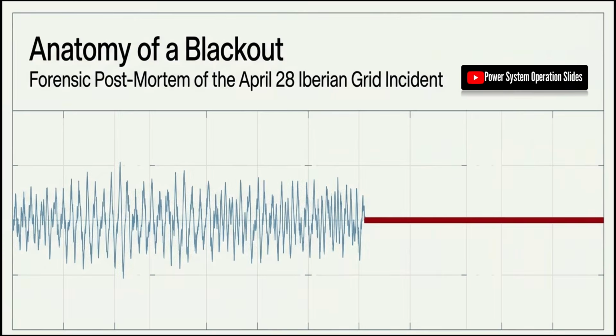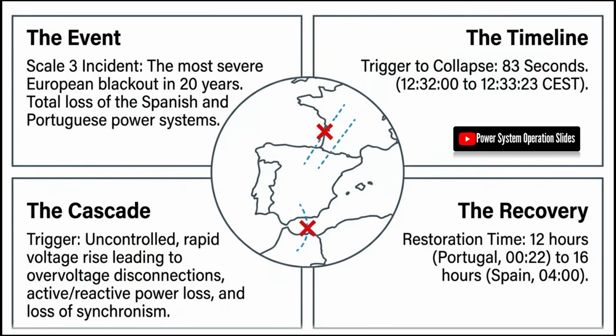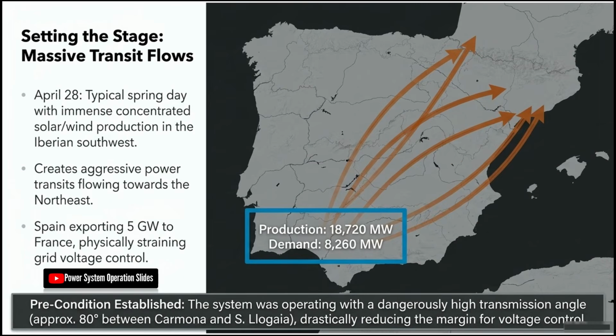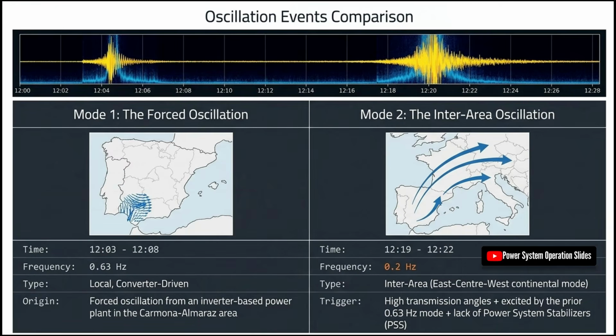To prevent future collapses, grids must adopt smart grid technologies, including synchrophasors and PMUs, which provide real-time visibility into grid dynamics. Wide area monitoring systems (WAMS) allow for the early detection of the types of oscillations that destabilize the Iberian grid, enabling automated damping responses. Dynamic security assessment (DSA) tools are also essential, allowing operators to run continuous N-1 and N-2 contingency analyses to identify vulnerabilities before they are exploited by a disturbance.